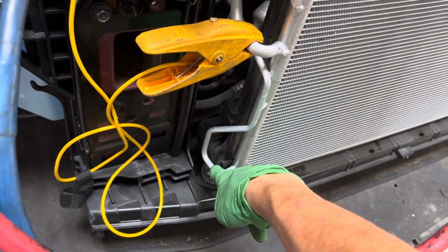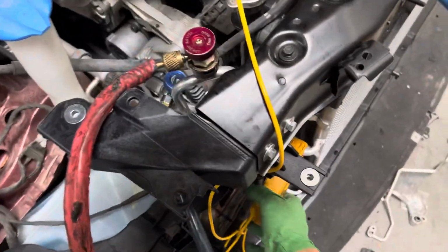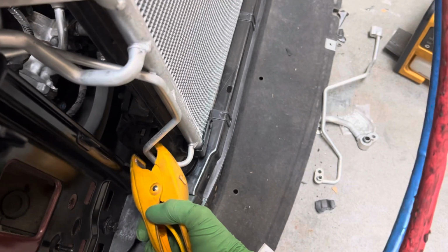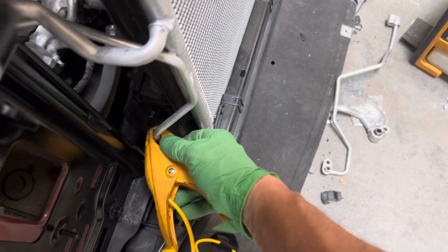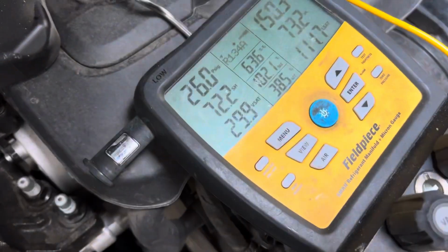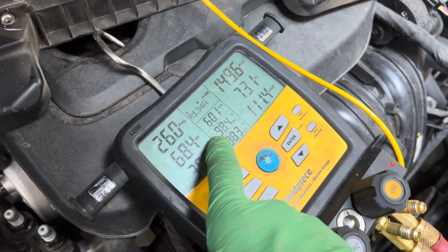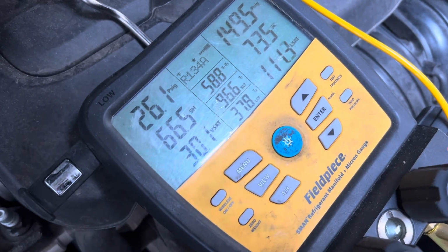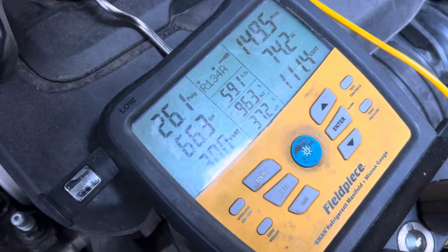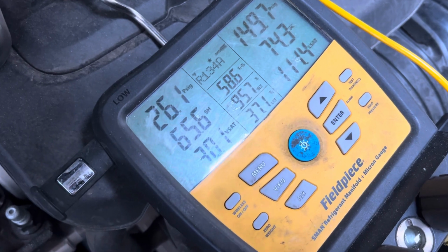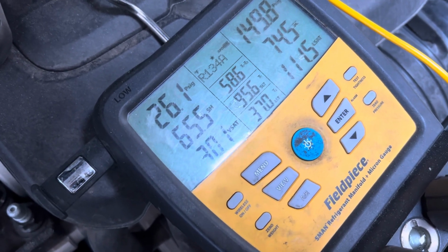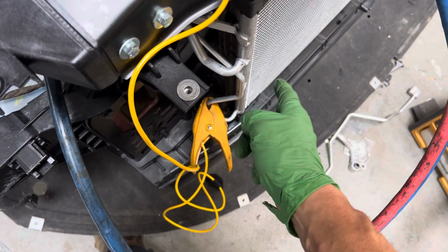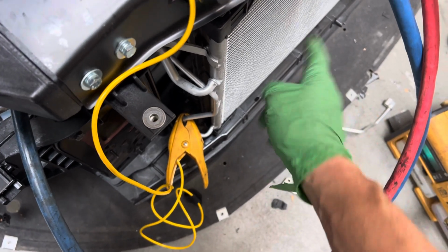So remember, it was 92 degrees right here. So let's grab this, and that was 140 degrees. Let's put it right here. Right there. There we go. It's dropping temperature because it's cooling off, because it was really hot from being on the 140 degree line. So you got to give it a little time. Let's call that good enough for government work. 95, it'll probably go down to 94 degrees. So let's round it off, just say 95 degrees. So it's 95 degrees exiting the subcooling part of the condenser.